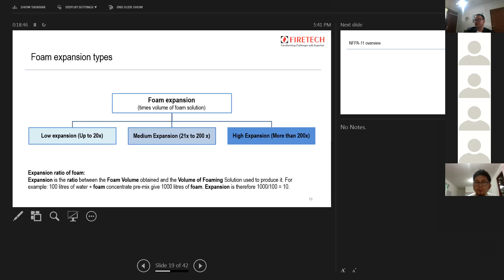So foam expansion means you get the total volume of that foam concentrate. Let's say 100 liters of water plus foam concentrate gives 1,000 liters of foam. So you divide the 1,000 liters of foam by the volume of water used, then you get the foam expansion. From this calculation, it shows 10, so it's categorized under low expansion.